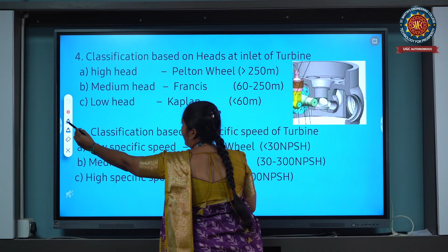The formula is Ns is equal to N under root of P by H to the power of 5 by 4, where Ns is the specific speed, N is the speed of the turbine, P is the shaft power, and H is the gross head. So this complete classification is based on this formula.